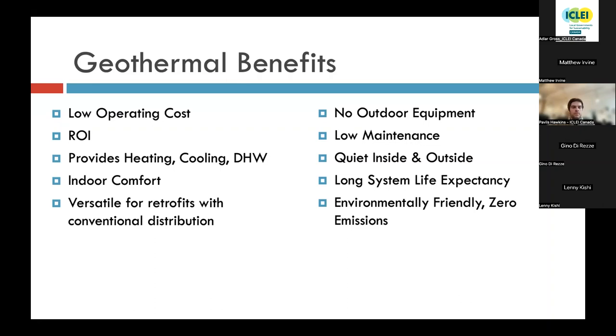Geothermal systems are versatile for retrofits with conventional distribution, both conventional ductwork, as was illustrated in that previous slide, as well as radiant systems, be they in-floor systems or radiant panels. There's no outdoor equipment, which is one of the reasons geothermal systems last considerably longer than a conventional furnace or an outdoor condensing unit for air conditioning, because they're just not subjected to the elements that conventional systems can be. This also results in very low maintenance.